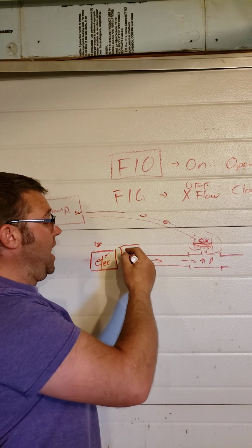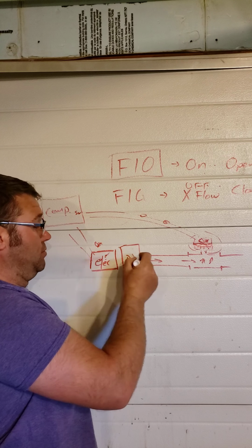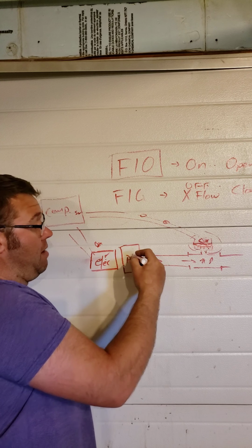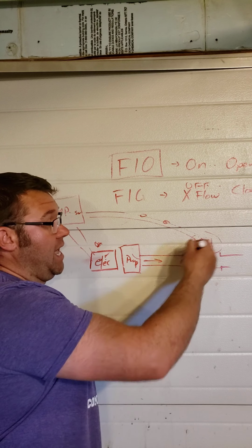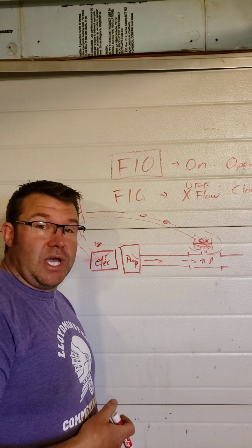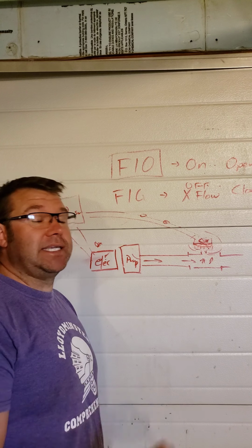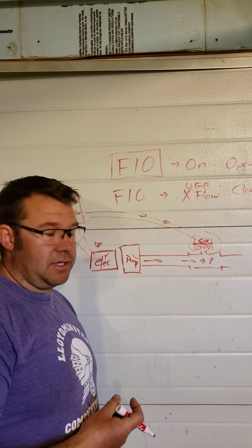Or the pump actually isn't running. So the motor is running, the computer thinks the pump's running because it's turned the motor on, but maybe the shaft's broken or the key's broken and I'm not getting flow, so then I can't get the pressure that I need. So one of those situations needs to happen, and this is identical to automotive computer system management, okay?